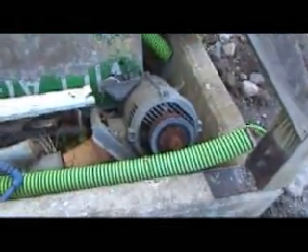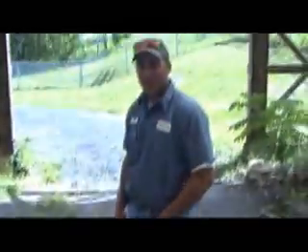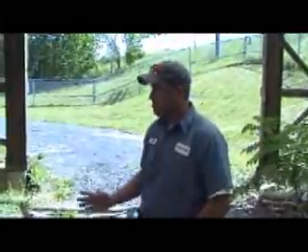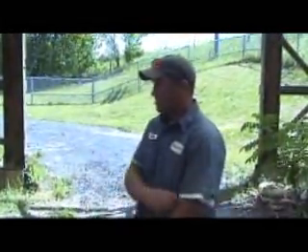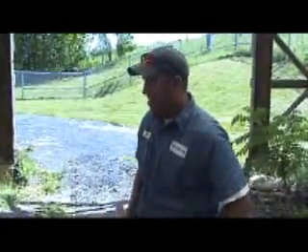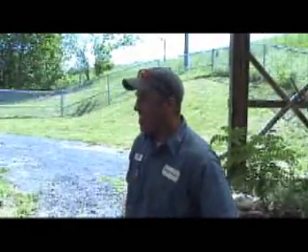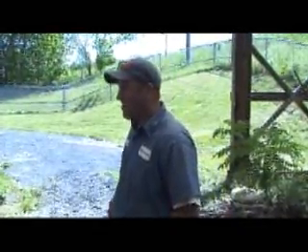This is the motor from the old blower, and there's what remains of it — not even a proper burial. It's going to the scrapyard. With those old ones, we were going through belts every four months. They were just coming apart. I think one of the problems was it was getting so hot in there — unbelievably hot — and the belts were just disintegrating. And I like how the new ones, you just jack it up and put the belts on. We haven't had to change anything yet.